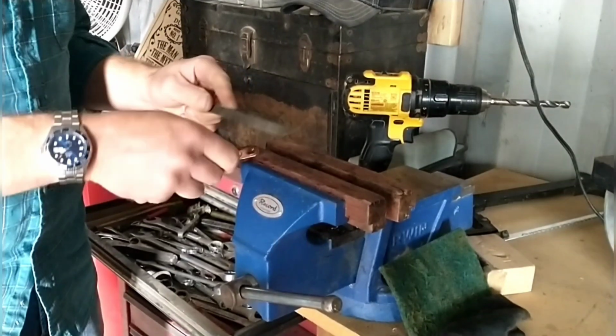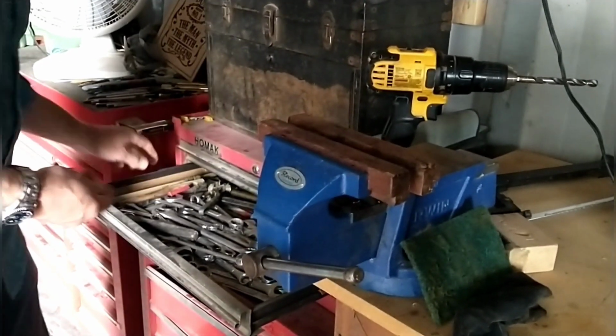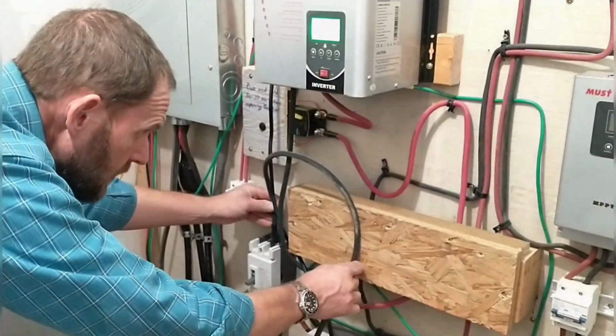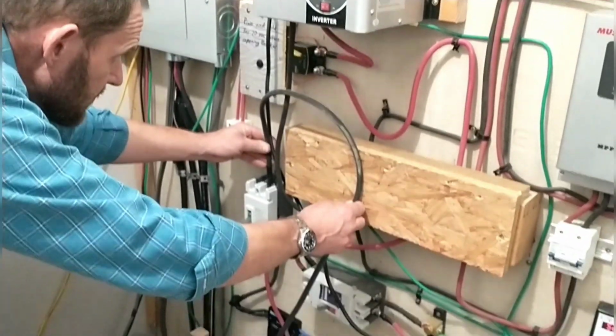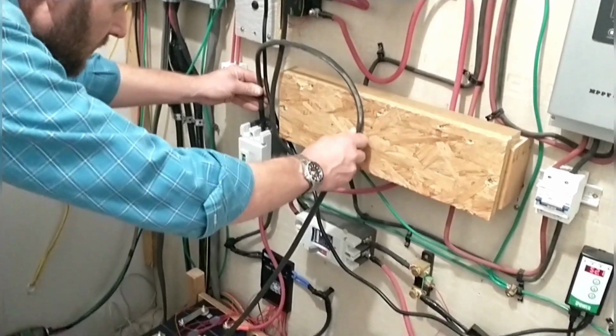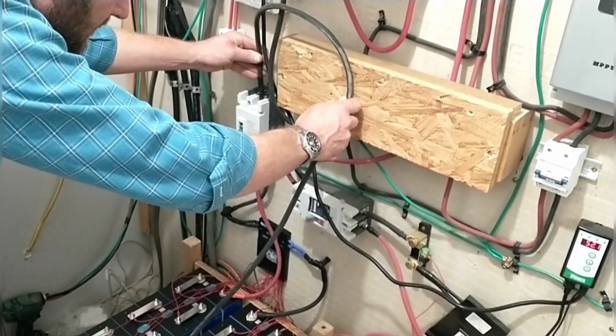April went over to the house to flip the water heater on so we could equalize the batteries, and while that's working, I'm modifying a couple of lugs. I needed a 3/8 inch hole instead of 5/16, so I just drilled it out. It didn't take long to finish making the last wires that'll connect the new components to the bus bars, and then I'm ready to check the batteries.